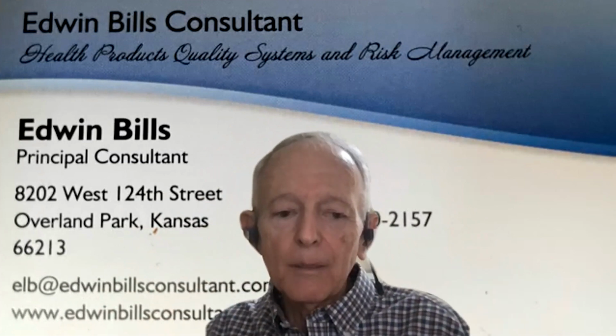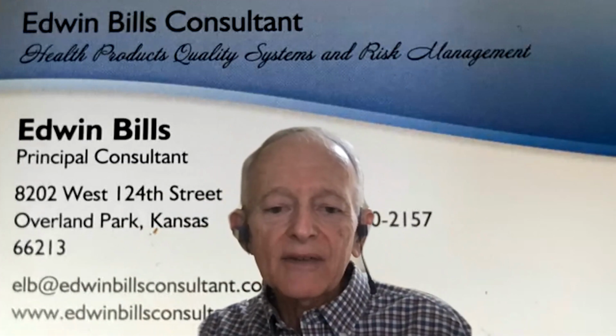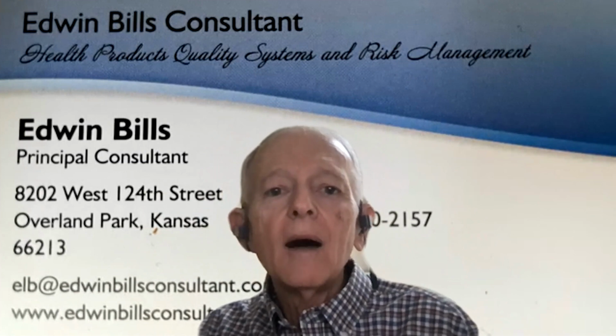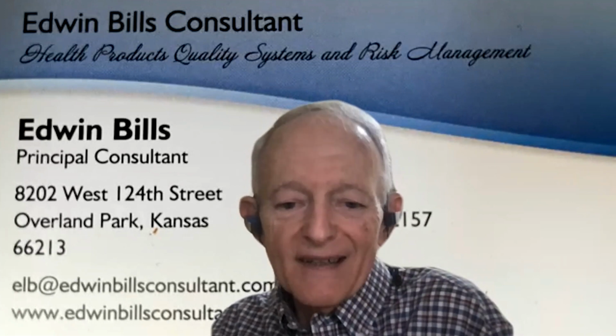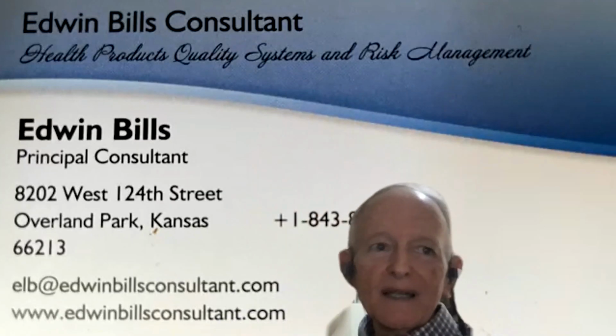So uncertainty is an important factor here. And there's a good question out there in the chat, Naveen, about benefit to risk, a term used in the MDR and 14971. What's the interpretation of this? The interesting thing is it's not defined anywhere. There's no definition that you can find of the term benefit-risk.